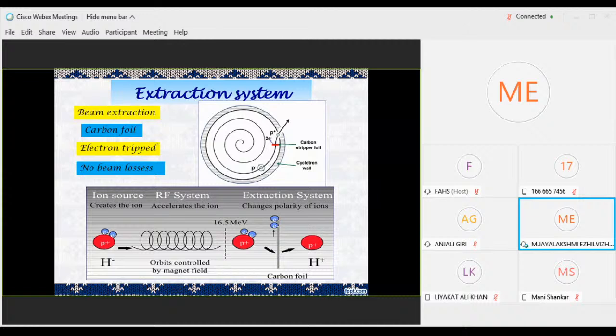I'll explain this. Look at this picture. At the ion source, as I showed in the Penning ion gauge, you have a positron with 2 electrons. When this is created, it accelerates because of the alternating current produced by the RF system. Then at the extraction system, you have a thin carbon foil. When the positron with the 2 electrons is accelerated to 16.5 mega electron volts, the 2 electrons are stripped off in the carbon foil, leaving only the positron. This is how the extraction system works.